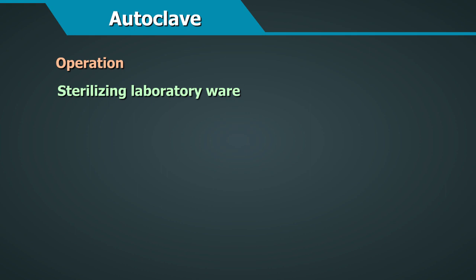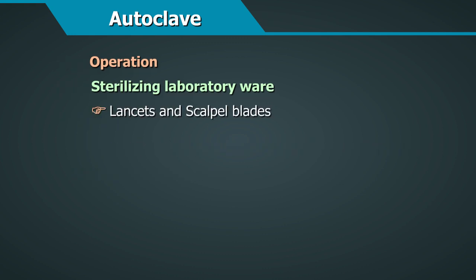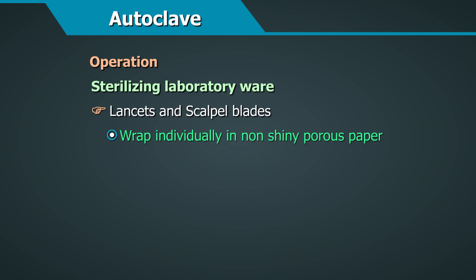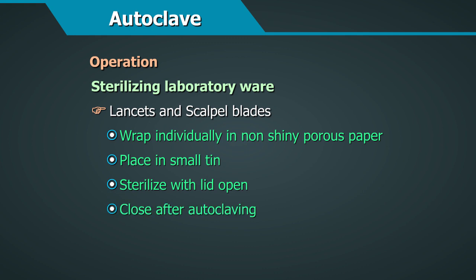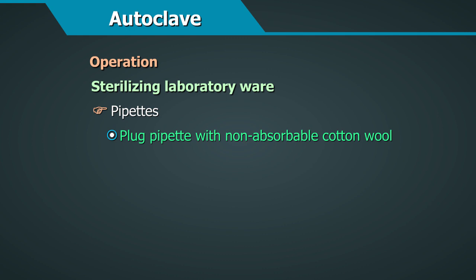When sterilizing laboratory ware, after cleaning, prepare reusable items as follows. For syringes, wrap polypropylene, nylon, or glass syringes with the barrel alongside the plunger in a clean cloth and close with adhesive tape or tie with a cloth strip. For lancets and scalpel blades, wrap stainless steel reusable lancets and scalpel blades individually in clean pieces of non-shiny porous paper and place in a small tin or other autoclavable container, sterilizing with the lid open and closing after autoclaving.